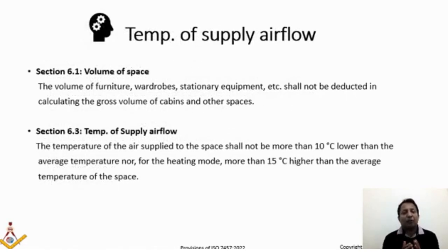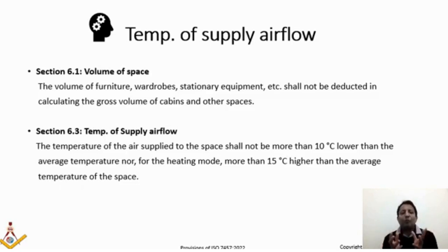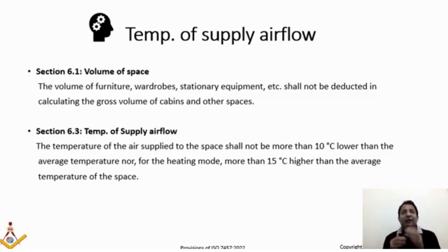Section 6.1 talks about volume of space. The volume of furniture, wardrobes, stationary equipment, etc. shall not be deducted when calculating the gross volume of cabins and other spaces. When calculating ventilation air using air changes per hour, you need the room volume — and it is strictly stated that you cannot deduct the volume of stationary items like chairs, furniture, or beds. You must consider the volume of a room as if it is an empty room.